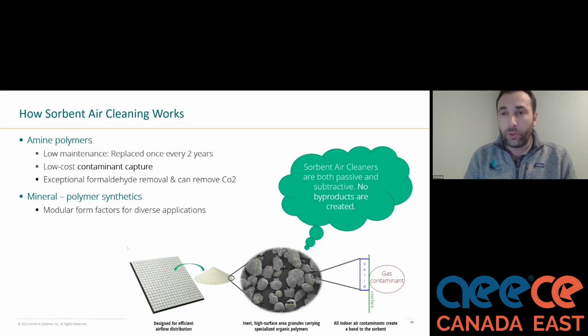These are both passive and subtractive. So typically you're going to couple this in a solution that has its own fan. That fan is going to overcome the static pressure drop across these filters themselves, and they're subtractive. What I mean by subtractive is that no byproducts are created during this process of capturing these contaminants. They do not need to be red bagged or red tagged during that once every 2-year maintenance cycle. So it's a very easy application to both apply and maintain.